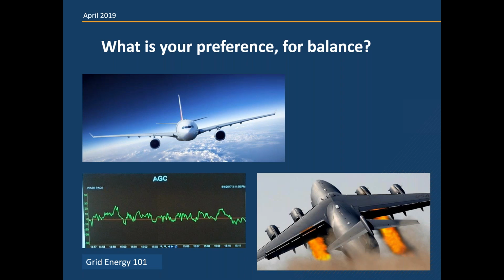But how we do that in real-time operations, you can see on the lower left-hand side of the screen, that's our ACE chart. And so you can see a faint red line, and that's the zero line. As long as that green line squiggles up and down across that red line as time passes, we're doing pretty good. If that line starts to go below that red line and goes south for quite some time, we're in a dive, and the system might go a little unstable. So his job to keep that balance of load and generation is going across that zero line as time progresses through the day. Next slide, please.